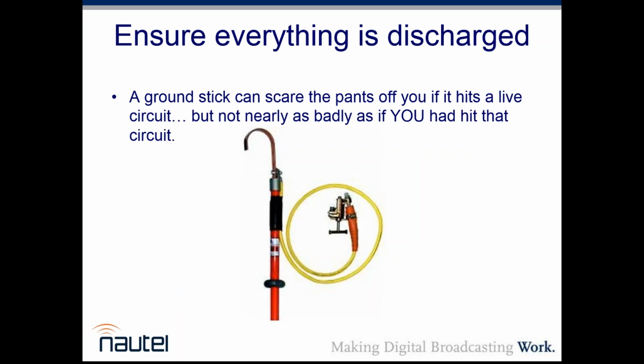I've had customers, even with ground sticks, that have gone through after they shut everything down. They went through with the ground stick, grounded everything, and had a broken wire in a lug where they came across and found 5,000 volts, which will lead me to a couple of slides.